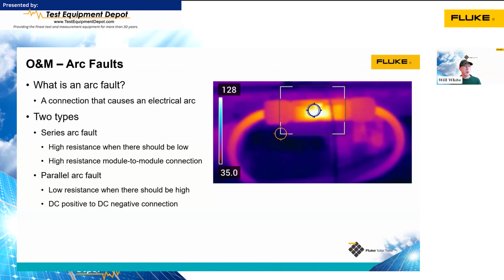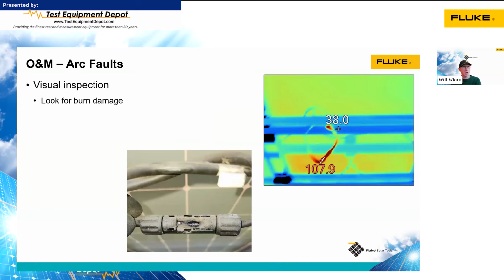Now, the second type of arc fault is a parallel arc fault, and this is low resistance where there should be high resistance. A good example would be a DC positive to a DC negative or AC line 1 to line 2. This is 2 current carrying conductors that have become connected. So there should be high resistance between those 2 connectors, and there's not anymore. Most of these ground faults or arc faults will continue to arc until they burn themselves out. But between the start and that point, we may have some problems.